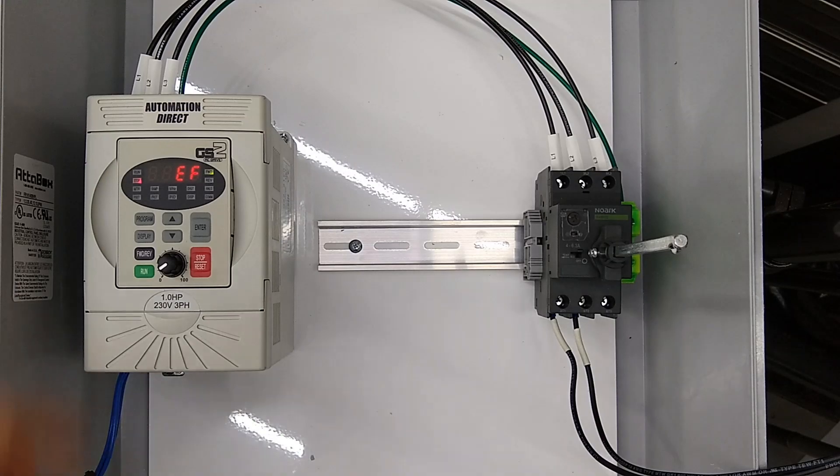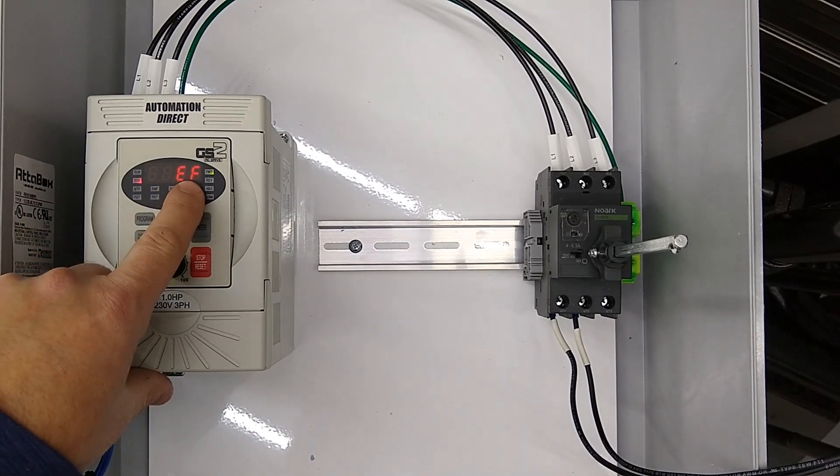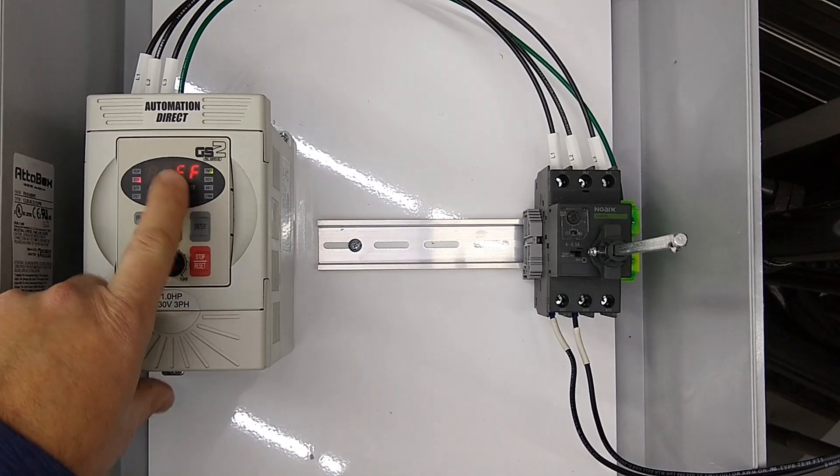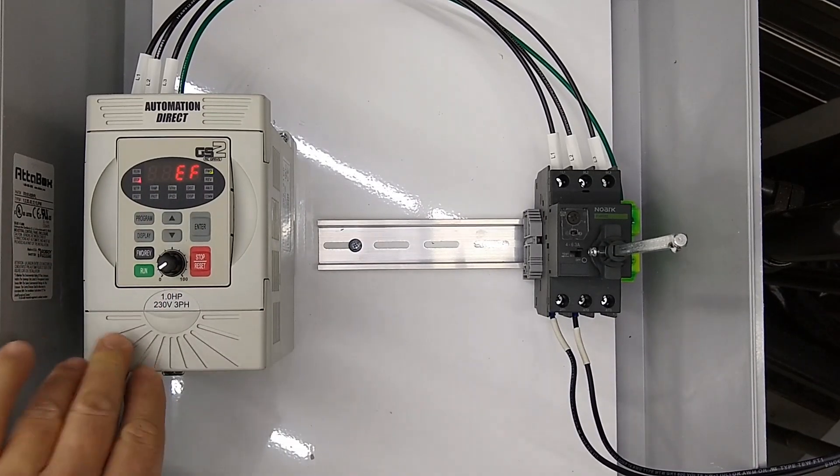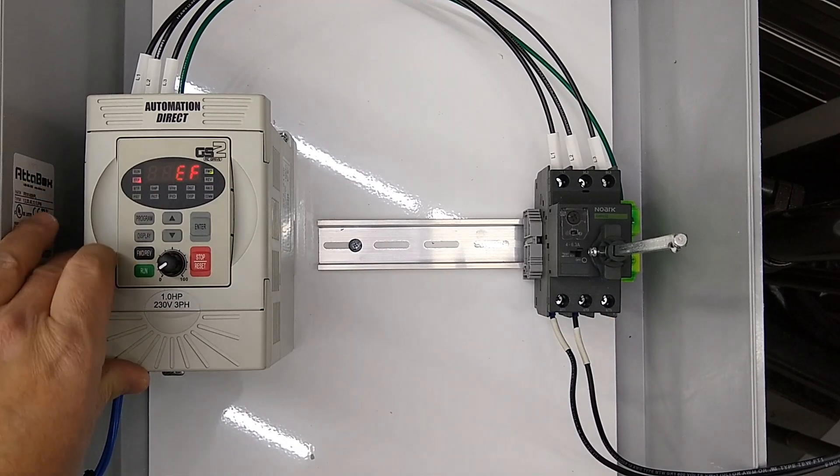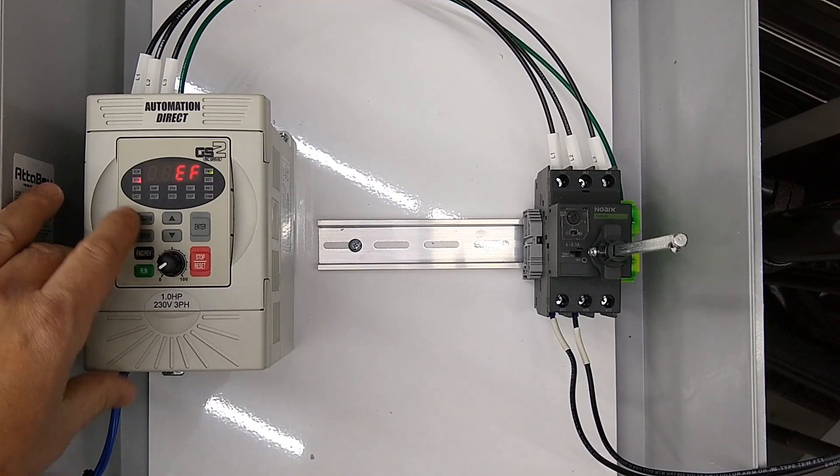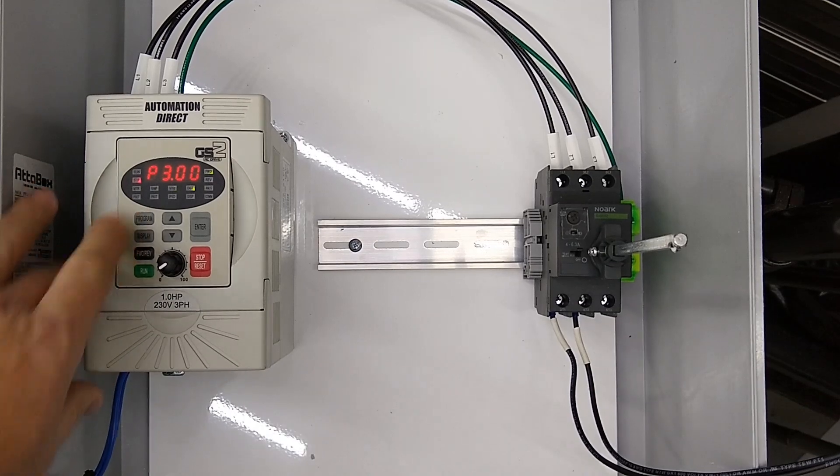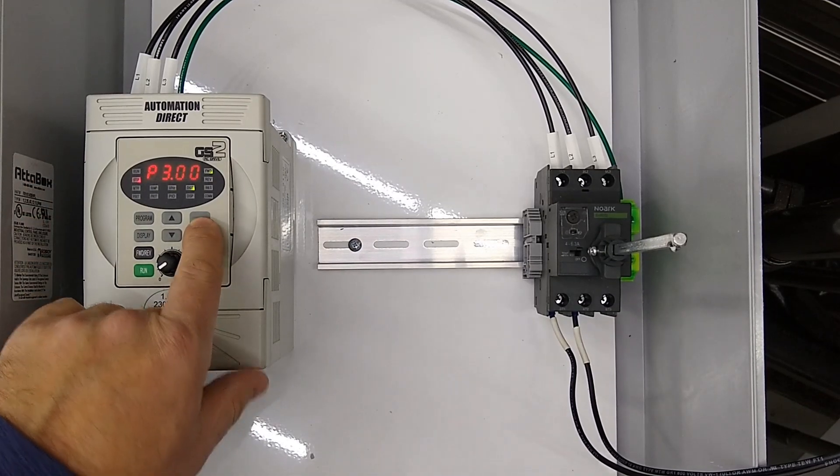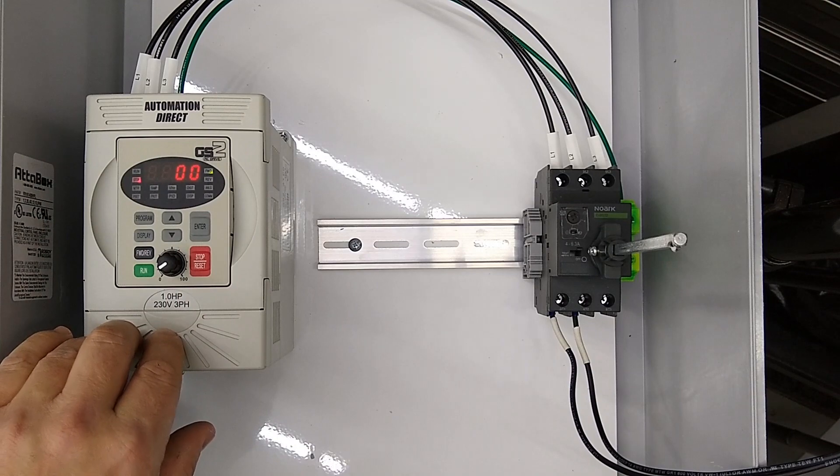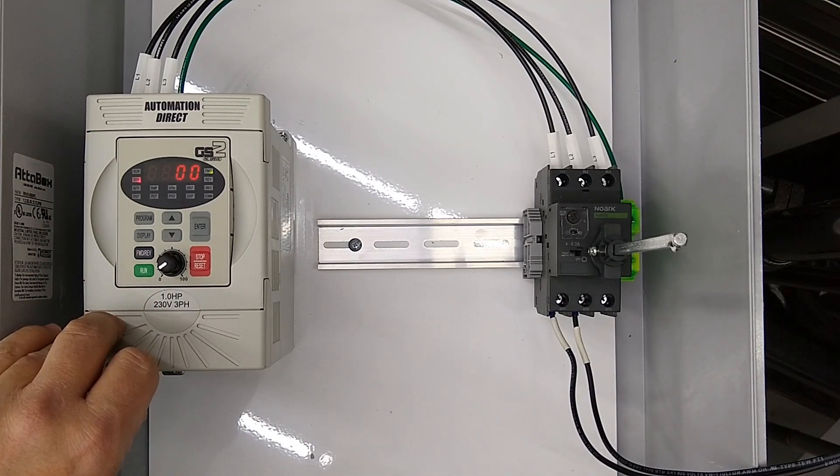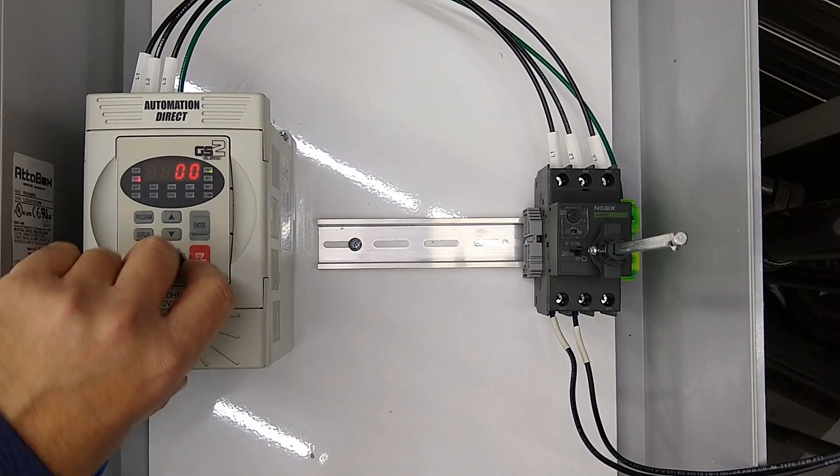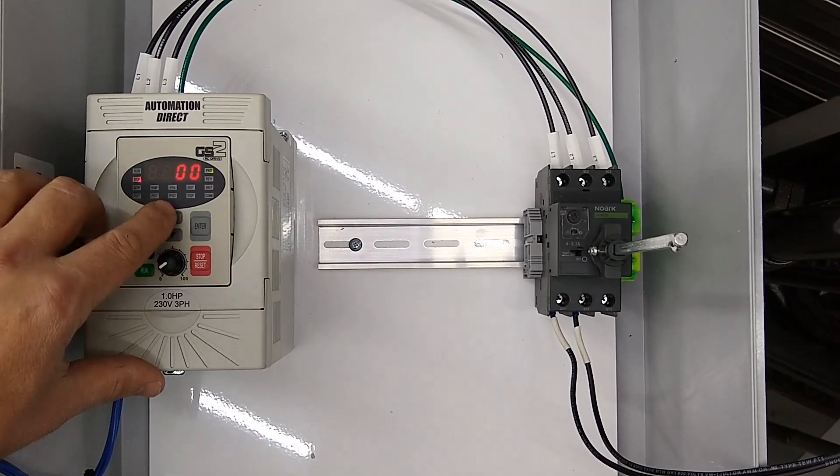Now if you have yours wired this way, when you power it up it's going to have an EF fault, and that's okay—we're going to take care of that with our configuration. The first parameter we're going to change is p3.00. Just hit the program button until you see p3.00 and hit enter. We're going to change this to a 2, which means operation is determined by external terminals and our keypad stop is disabled.